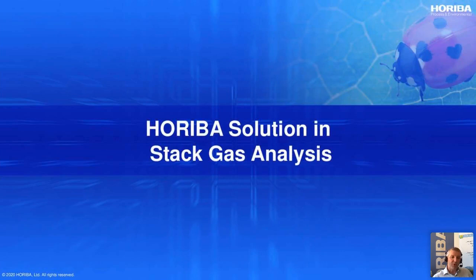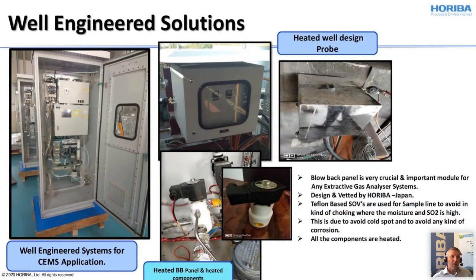So what is the HORIBA solution in the stack gas analysis? We have well-engineered solutions. You will have a questionnaire sheet where you need to fill in all the relevant information at the first level, so that our engineers can be on the safe side to plan the sampling system and to engineer the full system in the perfect way, so that the instrument and the full system will stand for more than 10 or even 20 years. We have a heated, well-designed probe. We have a blowback panel and so on. So everything is well designed from the beginning.